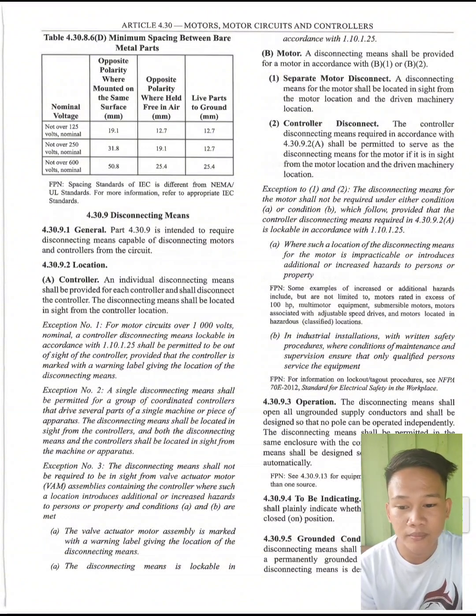Now, the exemptions. Exemption number 1: for motor circuits over 1000 volts nominal, a controller disconnecting means lockable in accordance with 1.10.1.25 shall be permitted to be out of sight of the controller, provided that the controller is marked with a warning label giving the location of the disconnecting means.